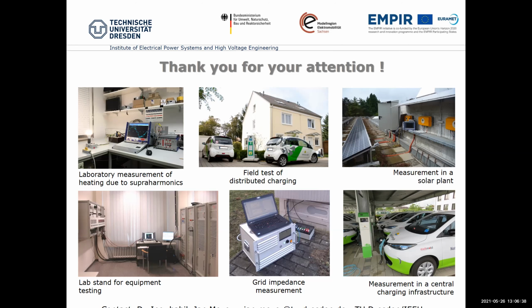The real measurement at the medium voltage side would require respective sensors that are able to measure accurately in the 2 to 150 kilohertz range. The classical instrument transformers that are used, the resin casted ones for example, are usually not capable of measuring those frequencies. So you have to set up an individual measurement setup, and this is a little bit difficult. I think Luleå University did some measurements, and also Ilmenau in Germany. We are currently doing something like that with a network operator, but it usually requires a lot of time nowadays.